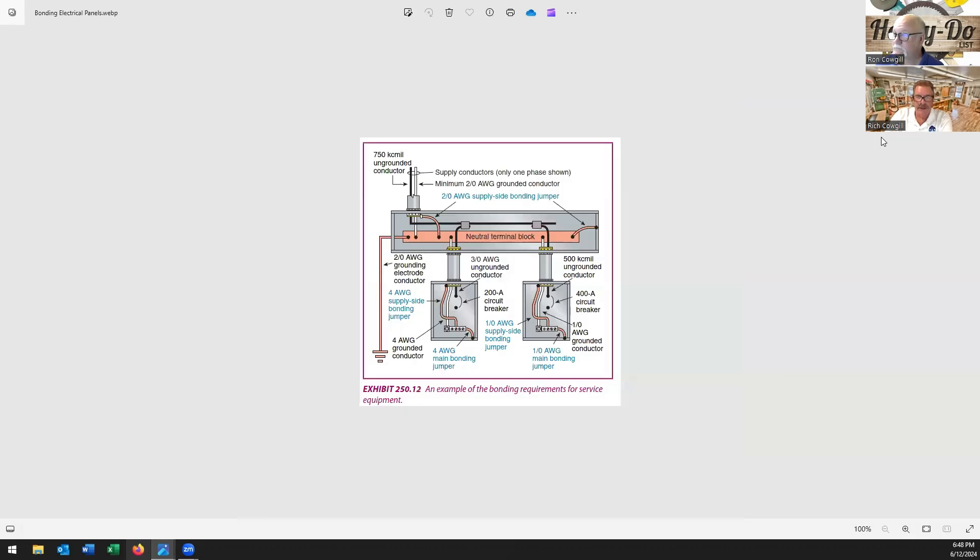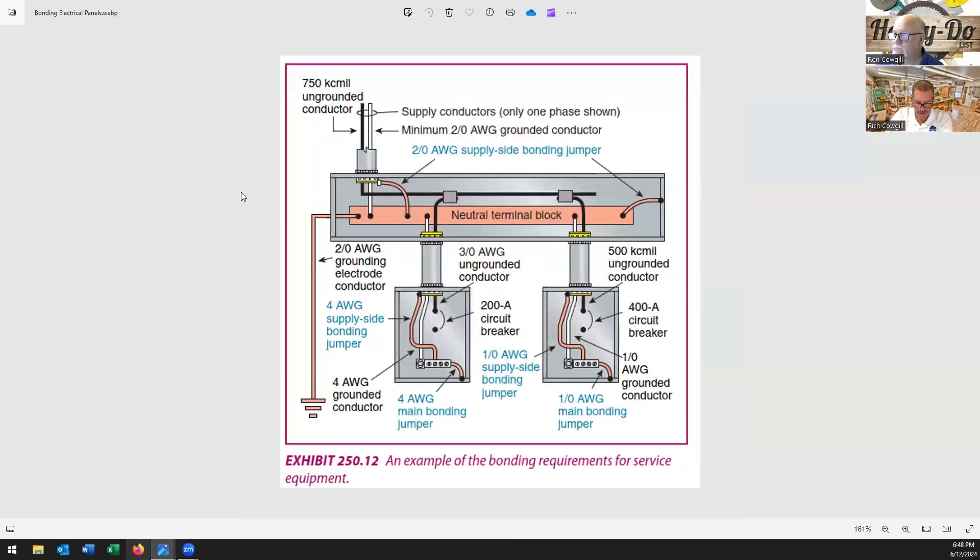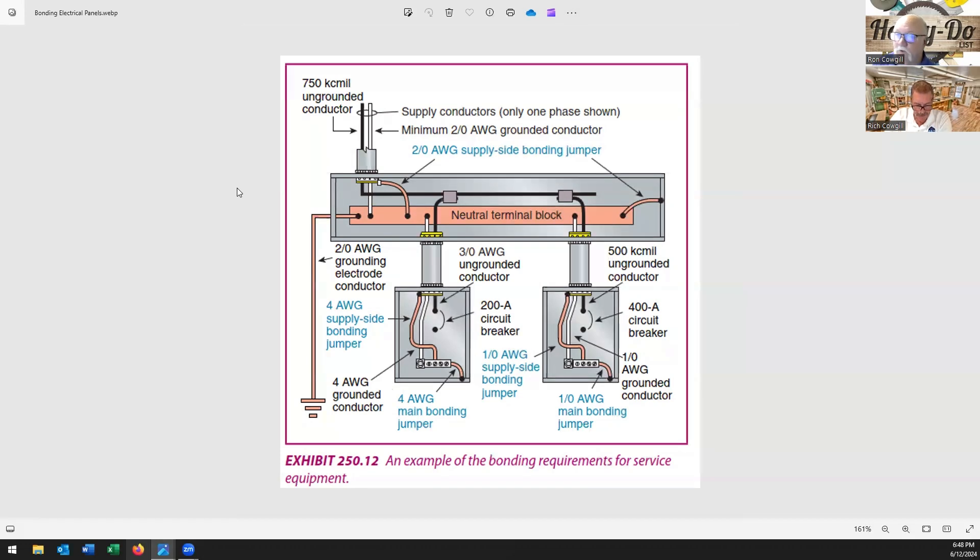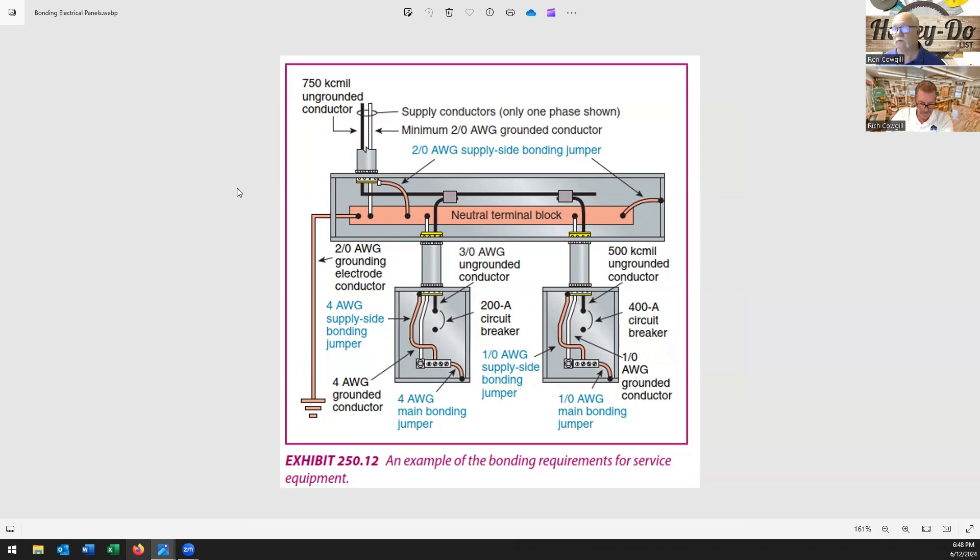So that brings us to bonding. Bonding - I like this definition actually. Electrical bonding is the practice of intentionally electrically connecting all exposed metal items not designed to carry electricity in a room or building as protection from electric shock. Bonding is also used to minimize electrical arcing between metal surfaces with electrical potential differences.